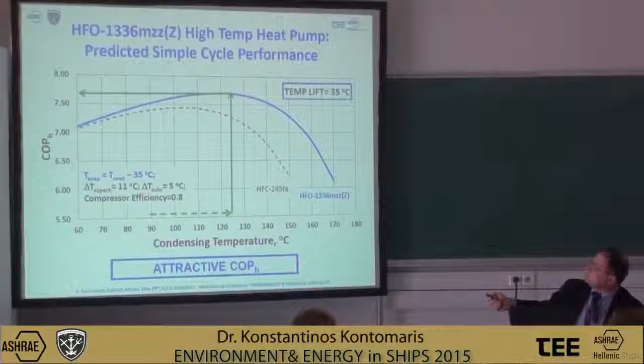What would the total losses be on that? A total loss? How do you define the loss? By converting it, what would the total COP be? The total COP, at least the ideal COP, so if you look at this example, let's suppose you take heat from the jacket water, which is at 90 degrees roughly, and you use a heat pump to lift it up to 125 degrees to generate low pressure steam. In this case, the theoretical COP will be 7.6, 7.7, which is a very high COP. Now, the actual COP, which accounts also maybe for frictional losses and the heat transfer losses, will be a little lower than that, but still very high and very attractive.